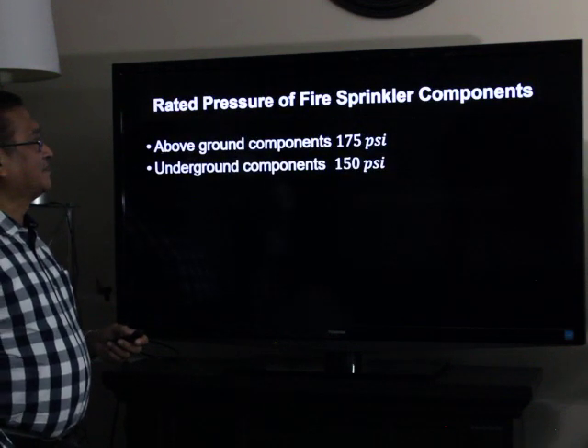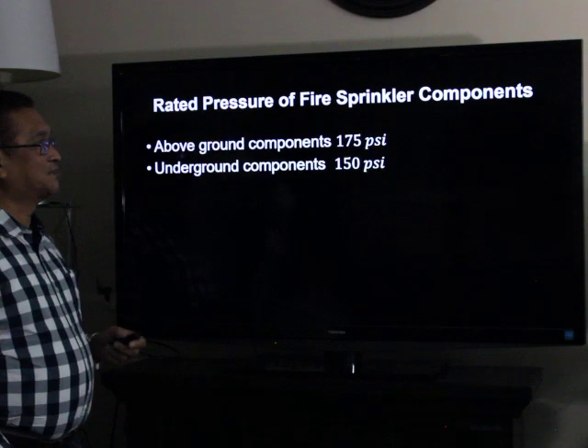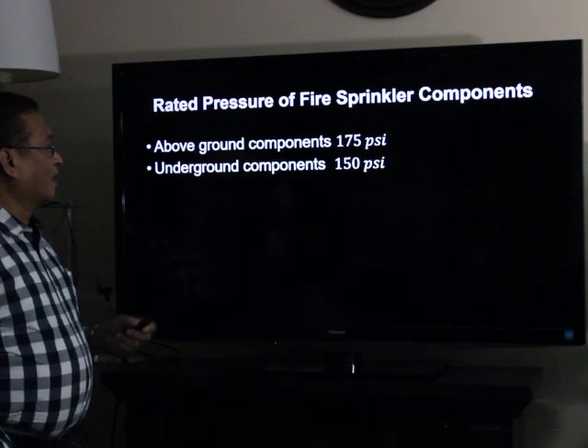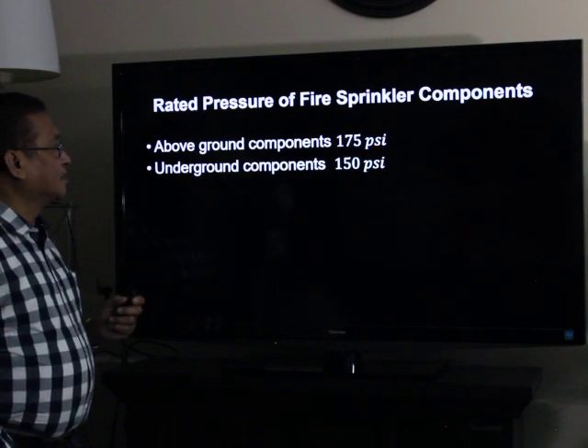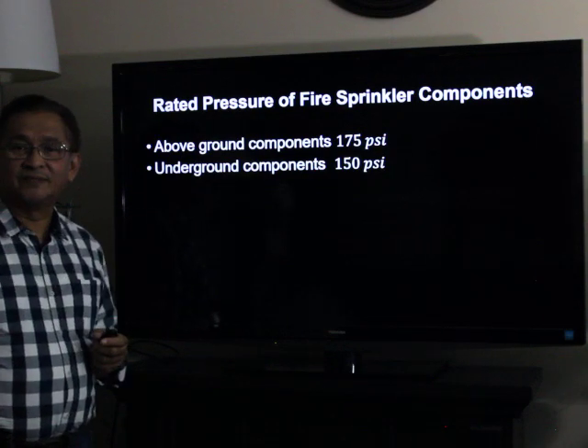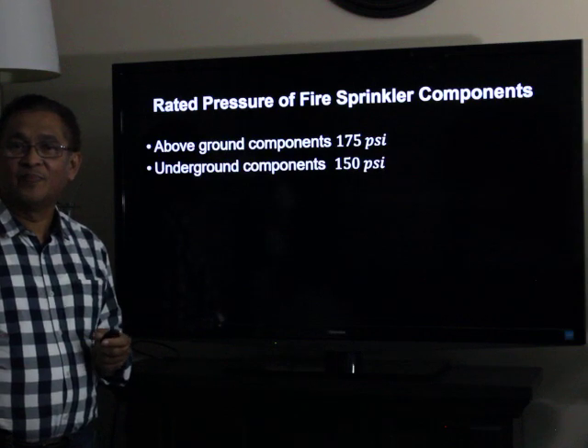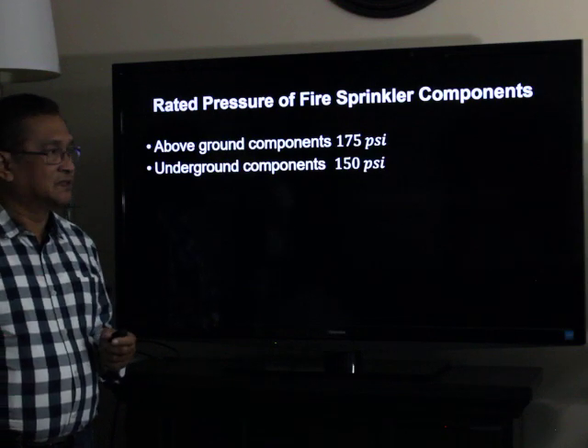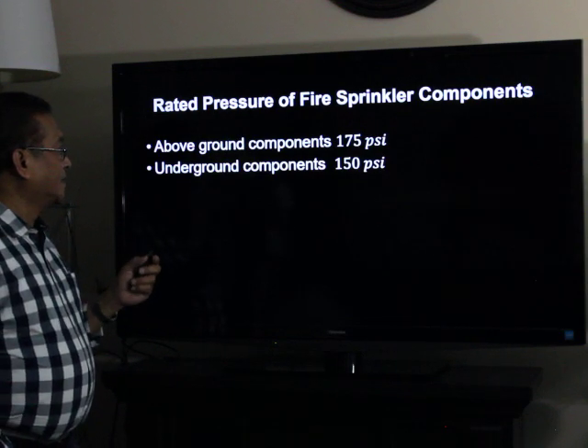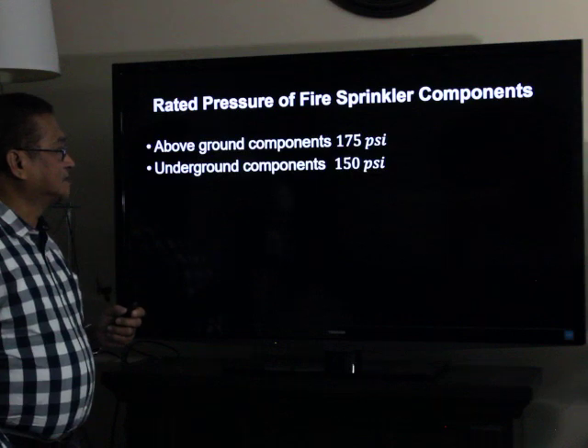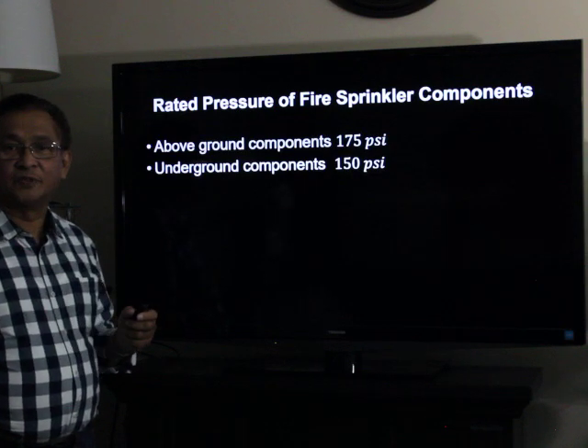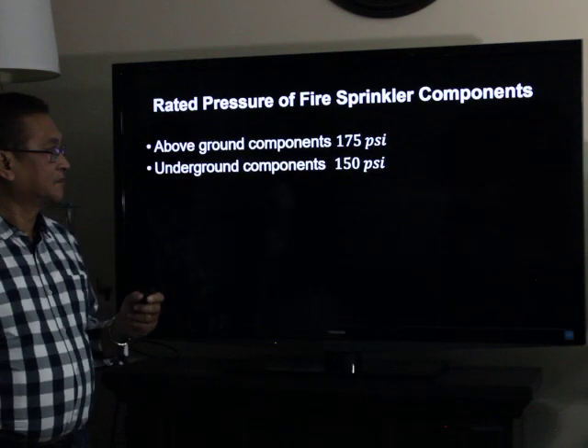Rated pressure of fire sprinkler components: for above-ground components, it is 175 pounds per square inch gauge. For underground components, it is 150 pounds per square inch gauge.